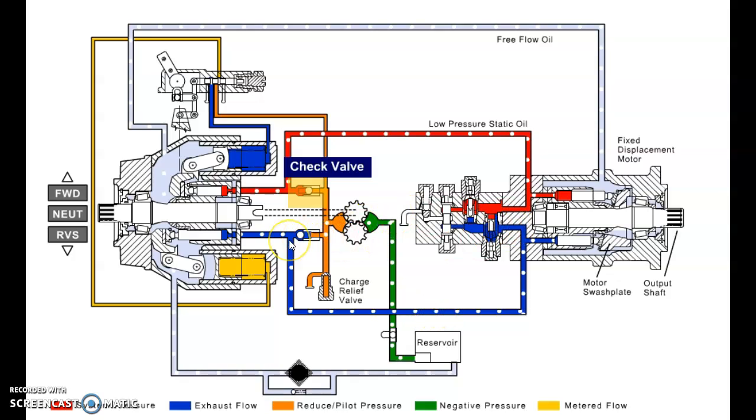The reason we need to replenish the loop and put oil in on the low pressure side is because we've got case drain at both the motor and the pump. We have case flow coming out of the motor traveling into the case of the pump, and then out the case drain line from the pump through potentially a cooler, and then back to the reservoir. That's what the charge pump is going to put back into the system.